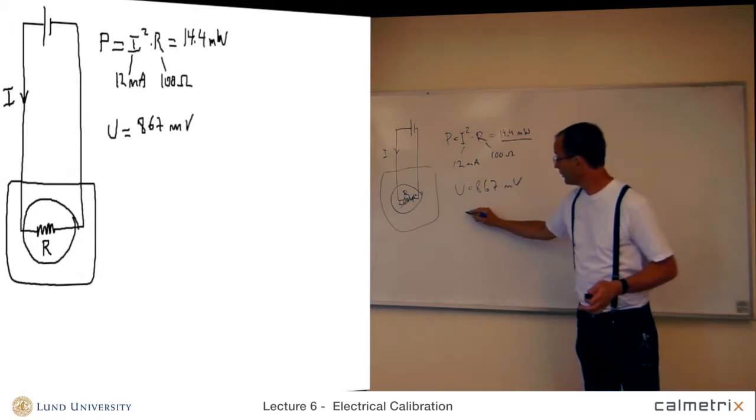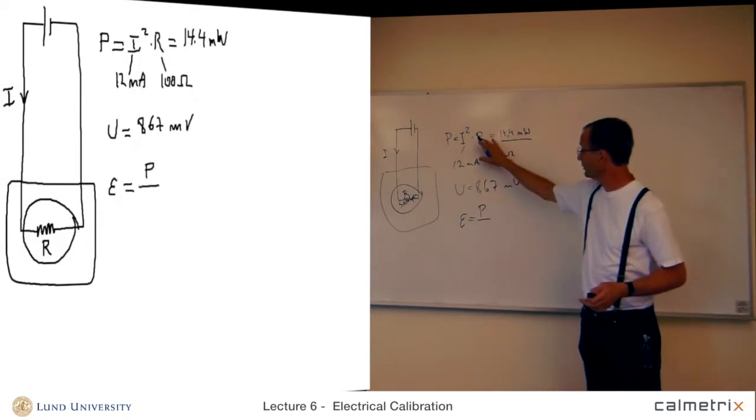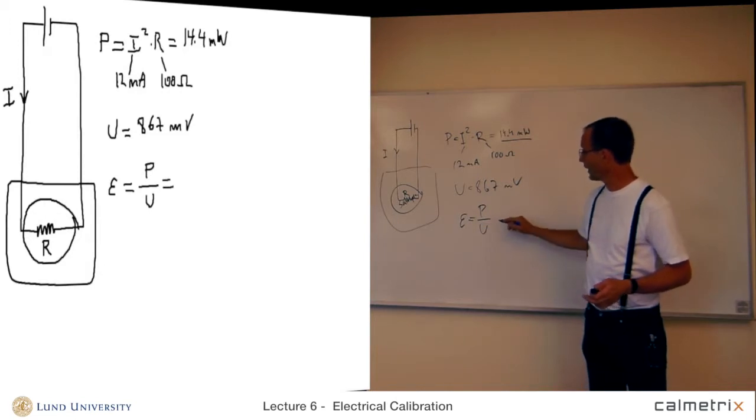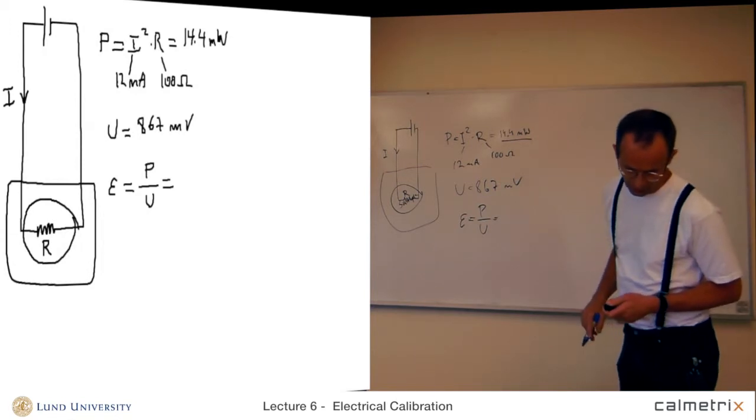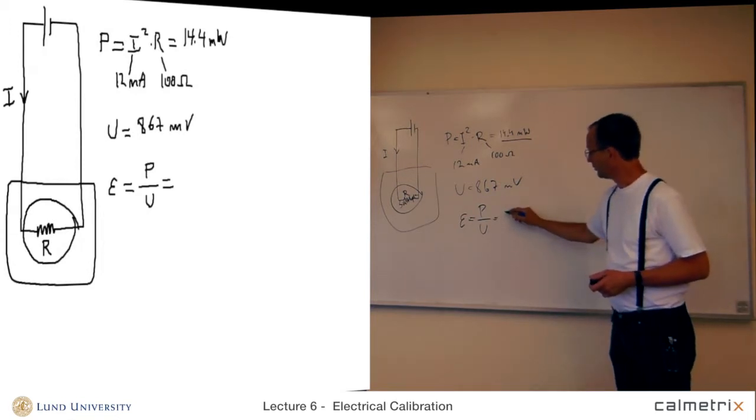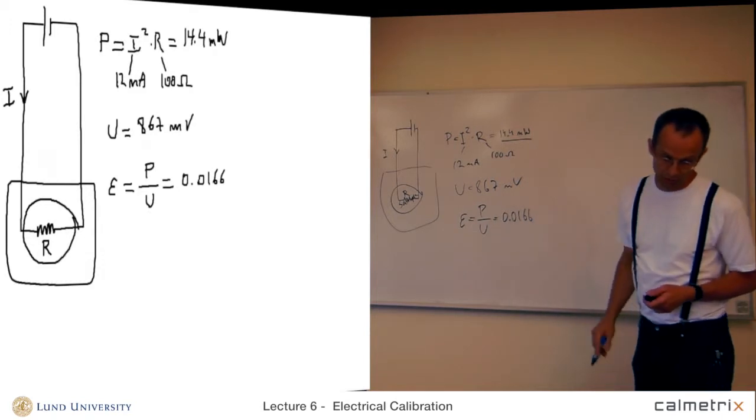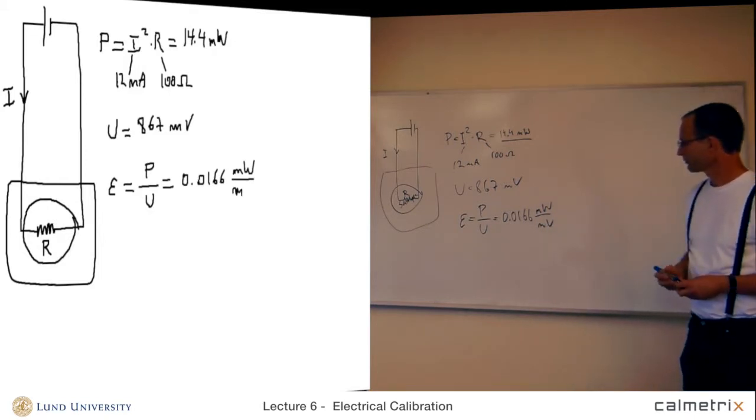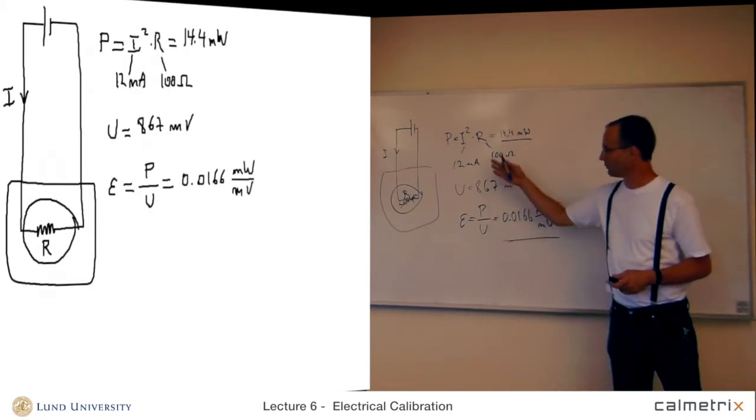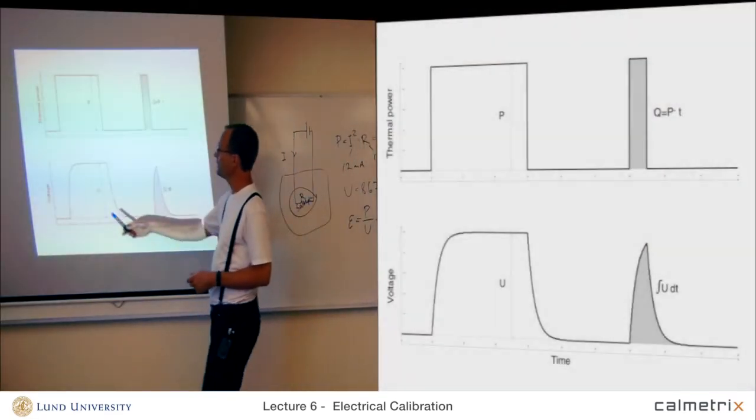Now, the calibration coefficient is the ratio of the thermal power produced and the voltage output. And in this case, if we divide these values, we will get 0.0166. And that is in units of milliwatt per millivolts. So, here we have found the calibration coefficient from an electrical calibration. Electrical steady state calibration, from this steady state.